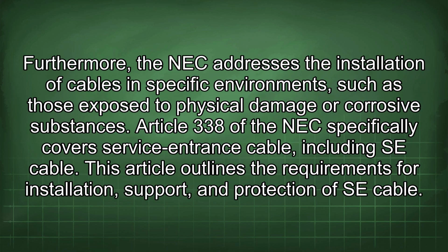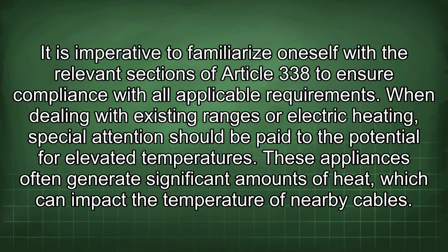Furthermore, the NEC addresses the installation of cables in specific environments, such as those exposed to physical damage or corrosive substances. Article 338 of the NEC specifically covers service entrance cable, including SE cable. This article outlines the requirements for installation, support, and protection of SE cable. It is imperative to familiarize oneself with the relevant sections of Article 338 to ensure compliance with all applicable requirements.